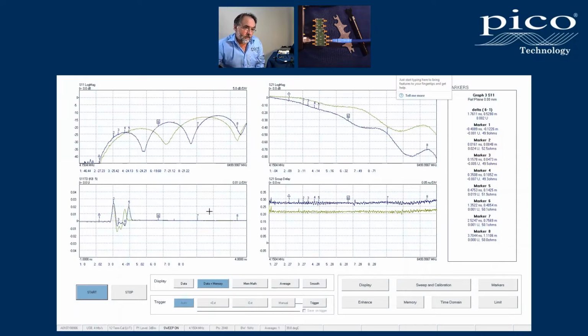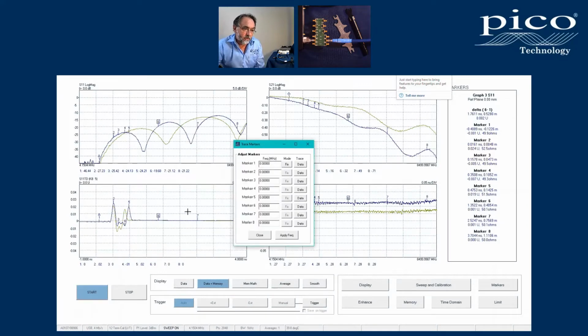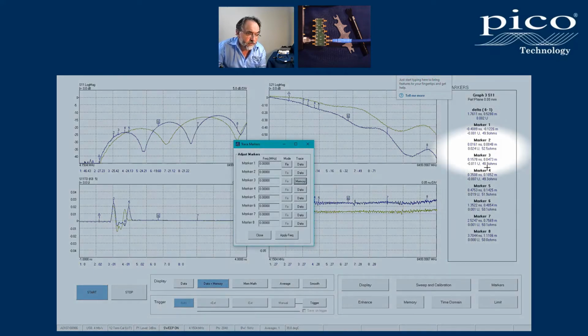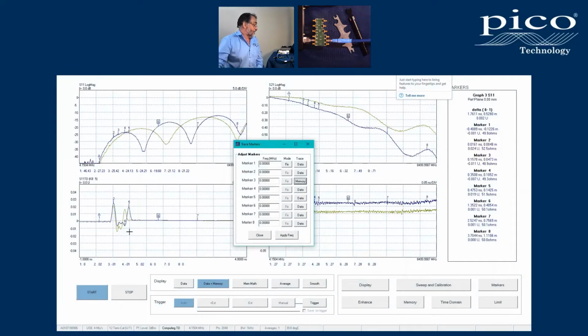We will just have a look. If I just take marker 3 and I put that onto the memory trace, we can see marker 3 now is 48.9. So here I can see that between two similar lines I do have a slightly different impedance of line on those two lines. It's really the impedance of the blue one that we're interested in. Oops. Back to data. 49.6 ohms there.